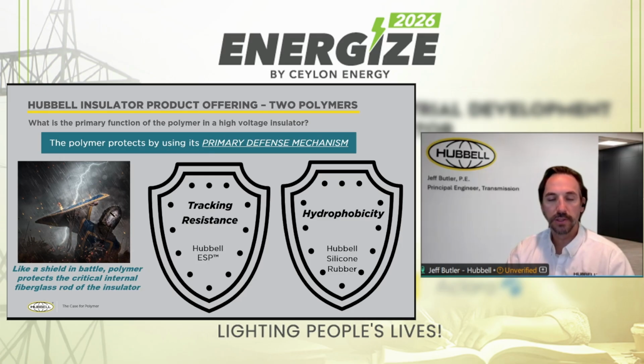On the other hand, when we're looking at silicone rubber, or specifically Hubbell's silicone rubber, the primary defense mechanism of silicone rubber is hydrophobicity, or the ability for water to bead on the surface, so that you're cleaning contaminants, you're reducing leakage currents, you're reducing that electrical activity on the surface of the insulator. So while ESP is able to withstand that electrical activity, silicone rubber, while still durable, the primary mechanism that it protects itself is the hydrophobicity of the silicone rubber. But it is important to understand hydrophobicity is a characteristic of silicone that can decrease and increase and recover. And so we need to look at the life of the polymer even in those moments where the hydrophobicity may be lacking under high electrical stress.